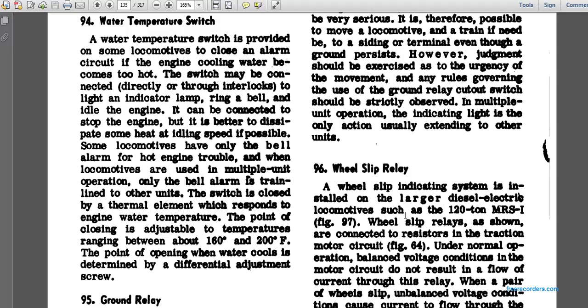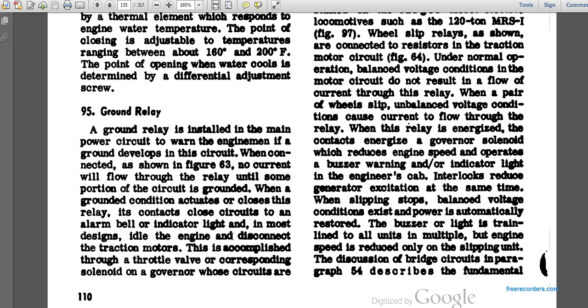Paragraph 94: water temperature switch. A water temperature switch is provided on some locomotives to close an alarm circuit when the engine cooling water becomes too hot. The switch may be connected to an indicator lamp, alarm bell, or engine idle circuit, or connected to stop the engine. Some locomotives have only a bell alarm for hot engine trouble. In multiple unit operations, only the bell alarm of the train extends to other units. The switch's closing point is adjustable, with temperature ranging between 160°F and 200°F.